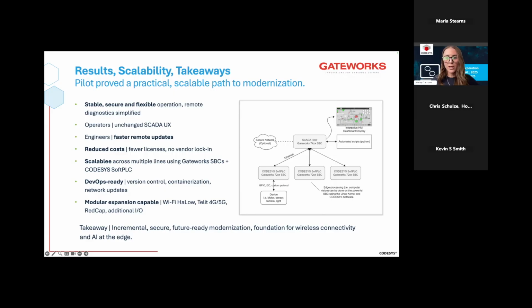Most importantly, the pilot became a template for their future expansion. Within six months, the customer rolled out the same CODESYS PLC configuration to other areas of the factory, all running on Gateworks Venice SBCs and standardized under one open software ecosystem. That is what modernization looks like in practice: incremental, secure, forward compatible. And it's not just about replacing old PLCs, it's about redefining that architecture to support future capabilities like wireless connectivity and AI at the edge.